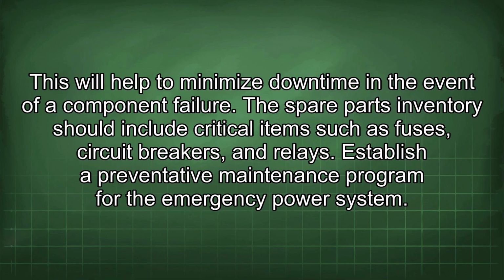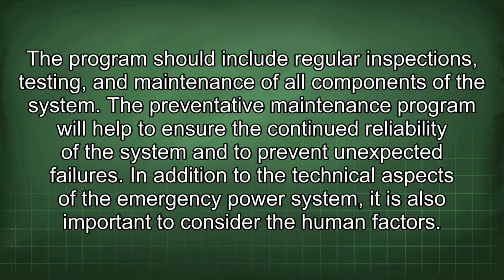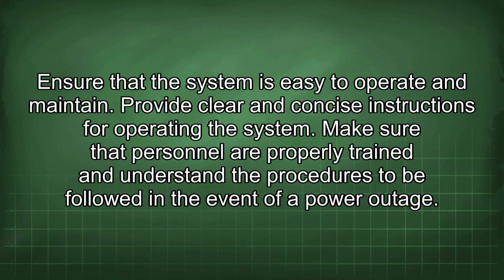Establish a preventative maintenance program for the emergency power system. The program should include regular inspections, testing, and maintenance of all components of the system. The preventative maintenance program will help to ensure the continued reliability of the system and to prevent unexpected failures. In addition to the technical aspects of the emergency power system, it is also important to consider the human factors. Ensure that the system is easy to operate and maintain. Provide clear and concise instructions for operating the system.